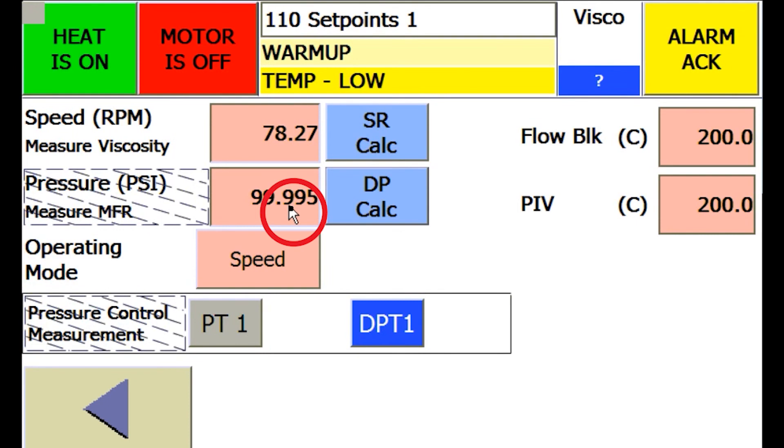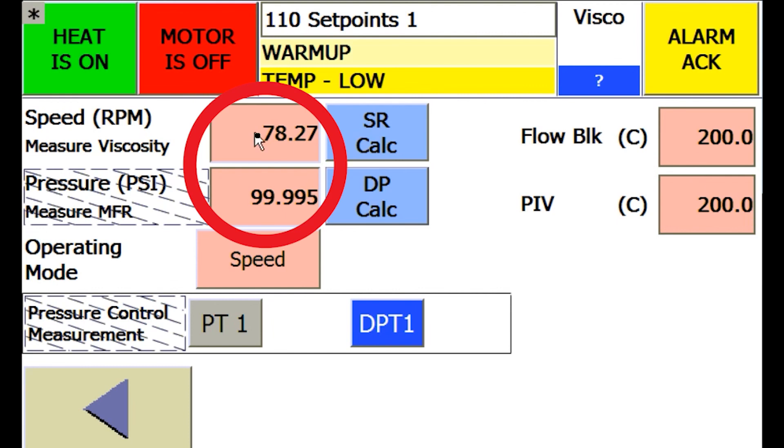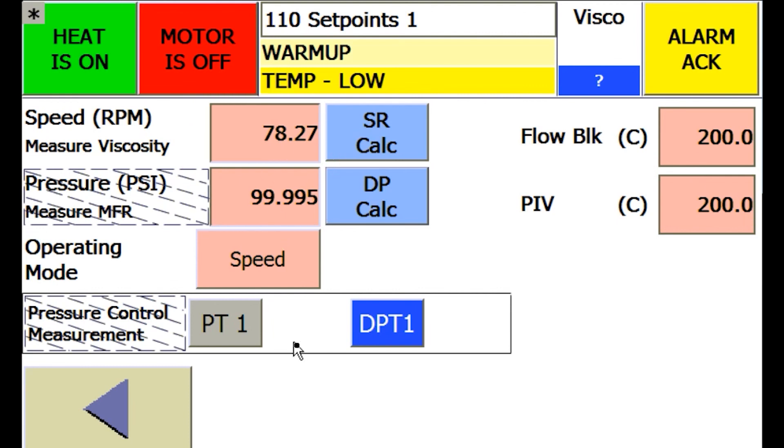The calculated pressures are derived from the installed capillary die's length and diameter. So now you have the system set to the temperatures you would like and the speed or pressure you would like the system to control to.